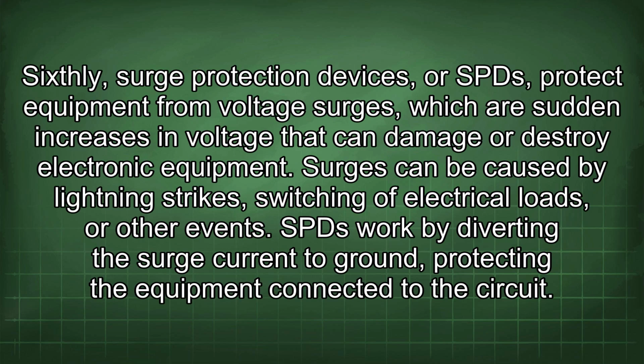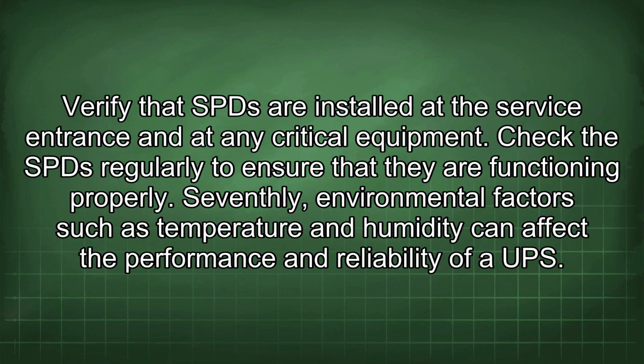Sixthly, surge protection devices, or SPDs, protect equipment from voltage surges, which are sudden increases in voltage that can damage or destroy electronic equipment. Surges can be caused by lightning strikes, switching of electrical loads, or other events. SPDs work by diverting the surge current to ground, protecting the equipment connected to the circuit. Verify that SPDs are installed at the service entrance and at any critical equipment. Check the SPDs regularly to ensure that they are functioning properly.